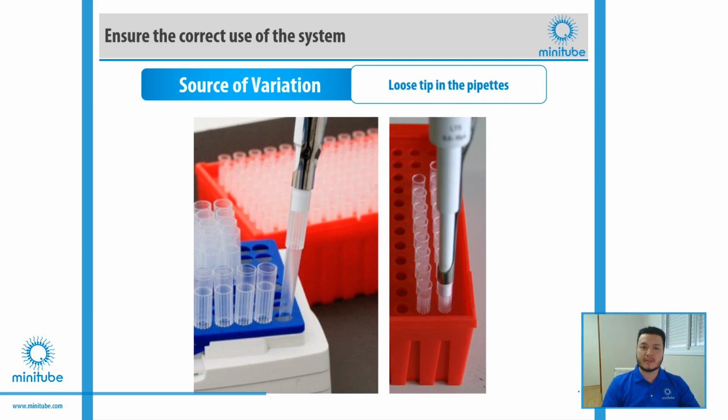Loose tip in the pipettes. This is a small detail that few people are aware of. Normally, taking the pipette tips from the boxes is so automatic and fast that we cannot imagine that this can represent a source of variation in the results. And then I will show you why this can happen.